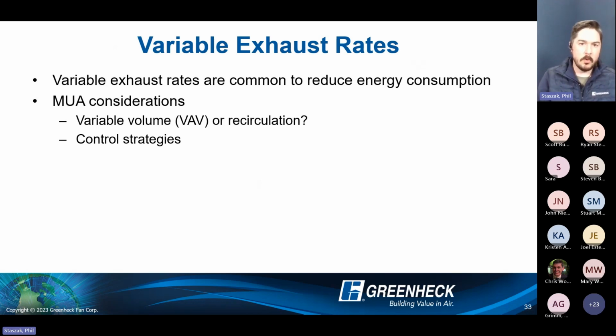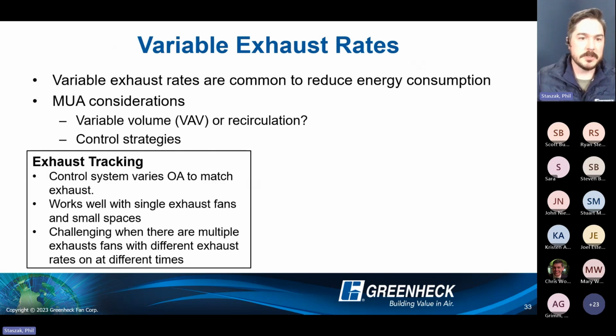Being able to physically reduce airflow up to 50%, or if you can recirculate 100% in an IGX selection, or up to 80% with a direct gas fired unit, the more air that you can recirculate, the less outside air is being introduced, therefore a lot less on the gas side of things. In a general heating application, there's less outside air to heat because you're just rotating through that 65-degree space condition already.